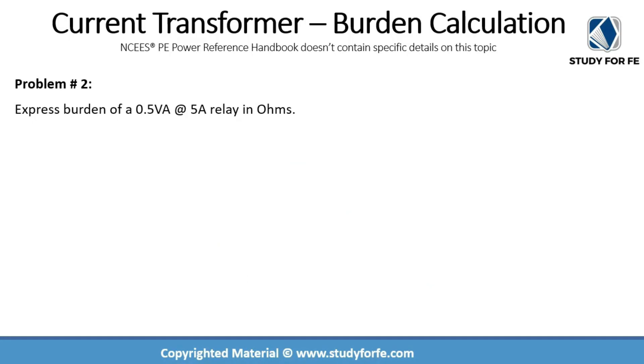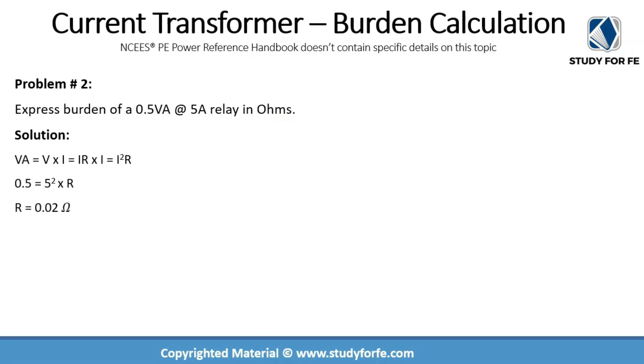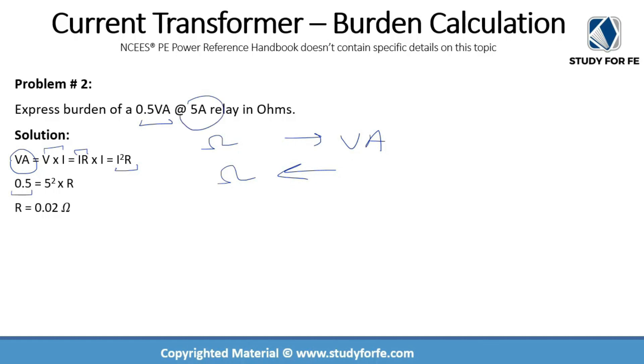Let us look at another practice problem where we are asked to express the burden in ohms, given the burden in volt-amperes at 5 amps. The burden is 0.5 VA. Since VA = I²R, we have I²R = 0.5. The secondary current rating is 5 amps, so I² = 25. Therefore R = 0.5 ÷ 25 = 0.02 ohms.